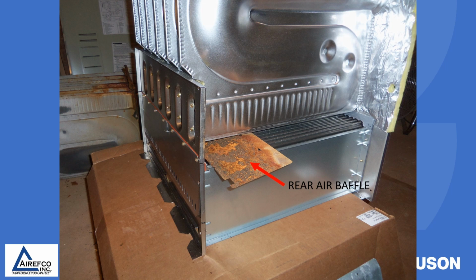This baffle is placed on top of the secondary heat exchanger in order to direct the air towards the front of the heat exchanger so that when the air passes over the high limit switch, it is at a temperature which will keep the furnace running. As you see, this rear air baffle can get corroded and rusted, and many times it may not be there when you do the service on the furnace.